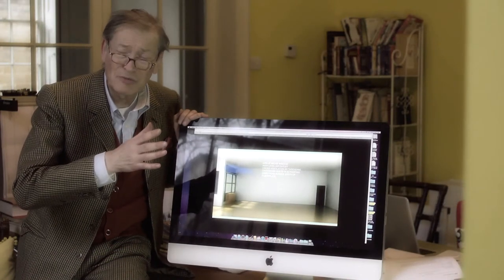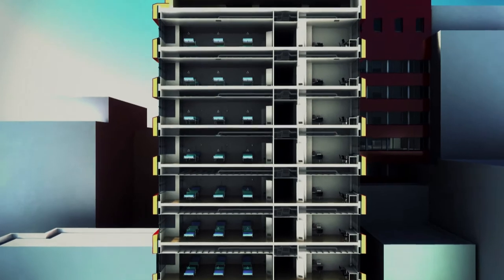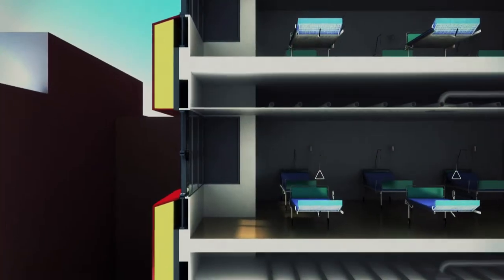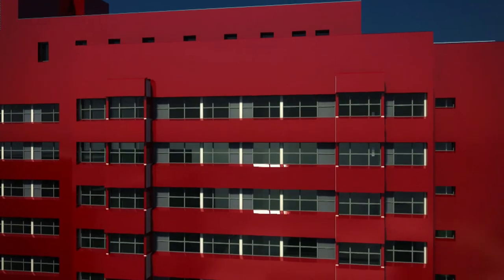Out of the research, we've looked at five or six principal building types across the NHS, diagnosed the data from them, and come up with various schemes. Option one pursues the industry standard — what an enlightened contractor might deliver. This is, in effect, the passive house model: a way of making very low energy houses translated into the world of public buildings. You put a duffle coat around the building, super-insulate it, seal all the windows, reduce the area of glazing as it's seen to be the weak link, and then pump air in and out through a very efficient heat exchanger.